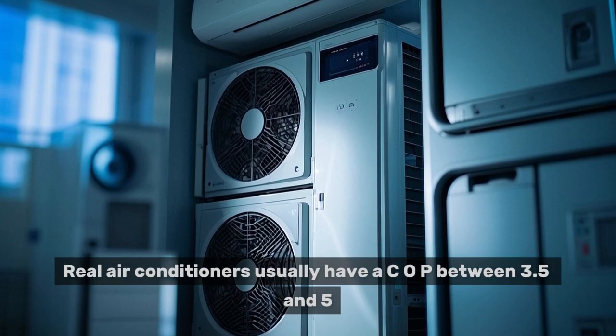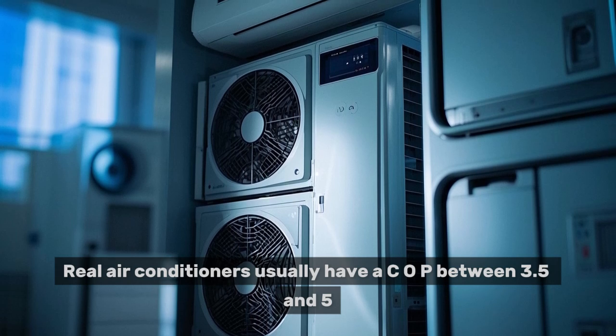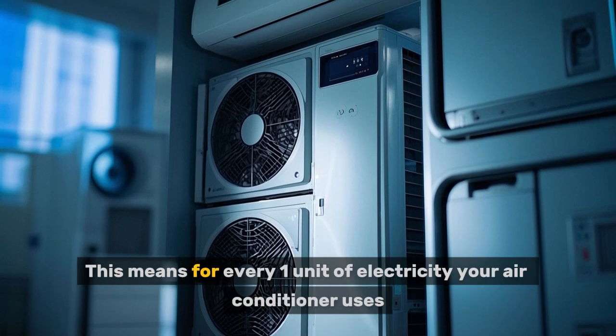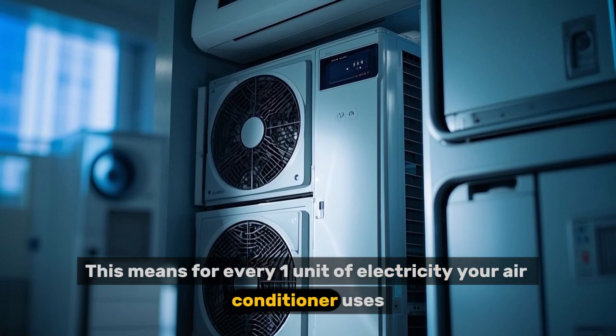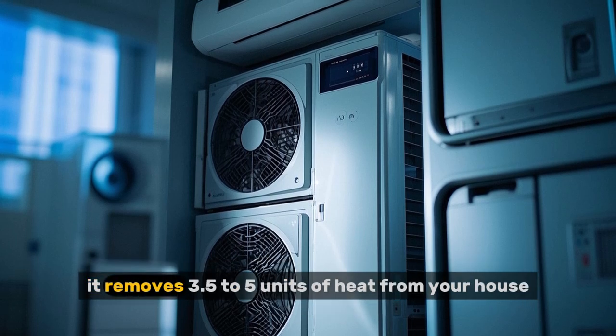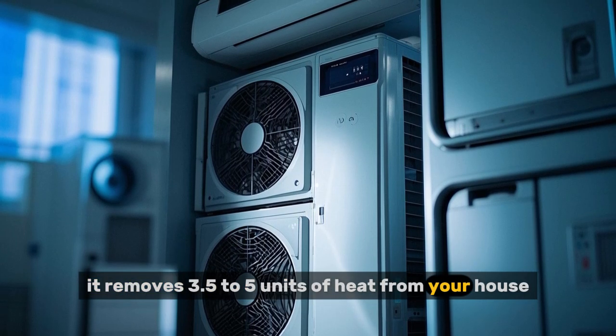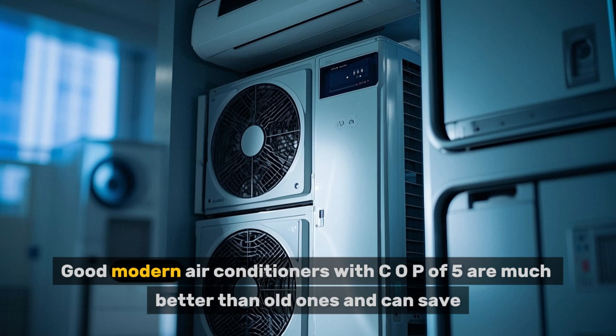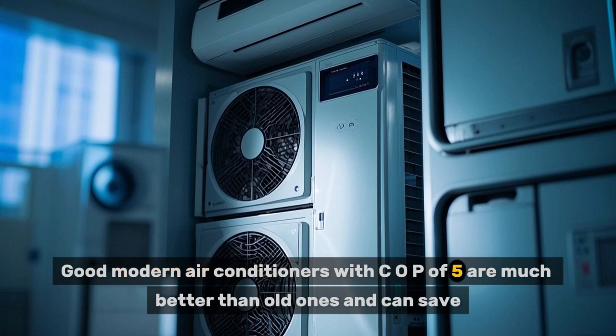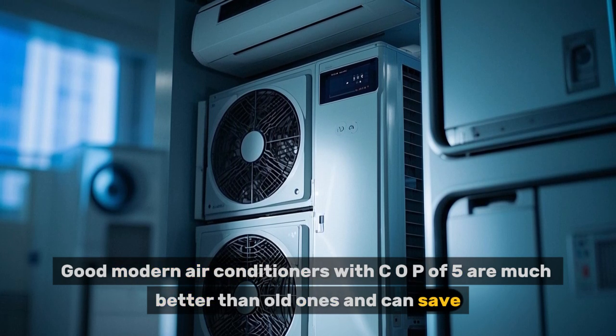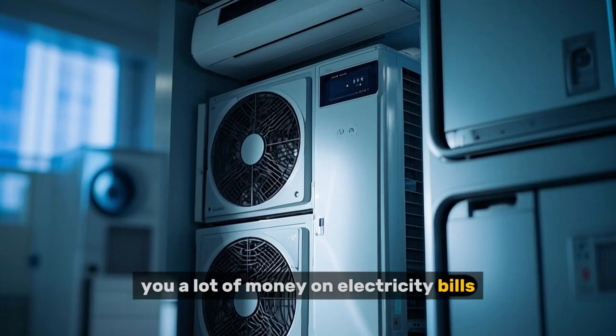Real air conditioners usually have a COP between 3.5 and 5. This means for every 1 unit of electricity your air conditioner uses, it removes 3.5 to 5 units of heat from your house. Good modern air conditioners with COP of 5 are much better than old ones and can save you a lot of money on electricity bills.